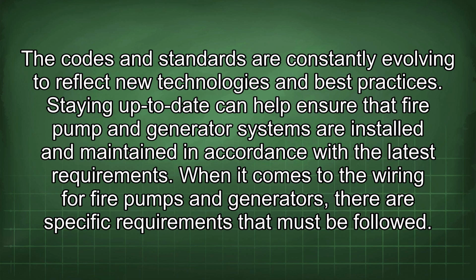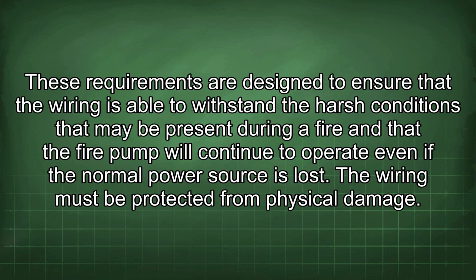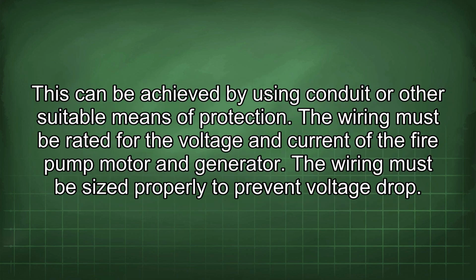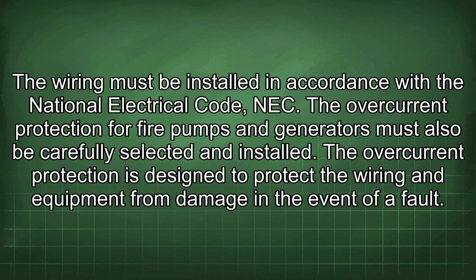When it comes to the wiring for fire pumps and generators, there are specific requirements that must be followed. These requirements are designed to ensure that the wiring is able to withstand the harsh conditions that may be present during a fire and that the fire pump will continue to operate even if the normal power source is lost. The wiring must be protected from physical damage. This can be achieved by using conduit or other suitable means of protection. The wiring must be rated for the voltage and current of the fire pump motor and generator. The wiring must be sized properly to prevent voltage drop. The wiring must be installed in accordance with the National Electrical Code (NEC).